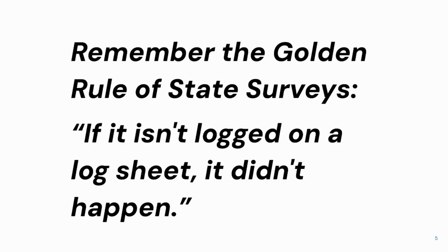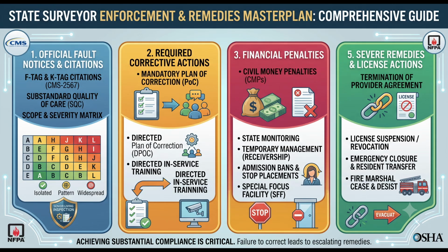Remember the golden rule of state surveys: if it isn't logged on a log sheet, it didn't happen. You could have serviced every nurse call button yesterday, but without a signed dated log, the surveyor will write it up as a failure every single time. 4 distinct agencies and 4 different sets of priorities. So what happens when these PMs get missed or skipped? Fines, citations, frozen admissions, and immediate jeopardy tags.